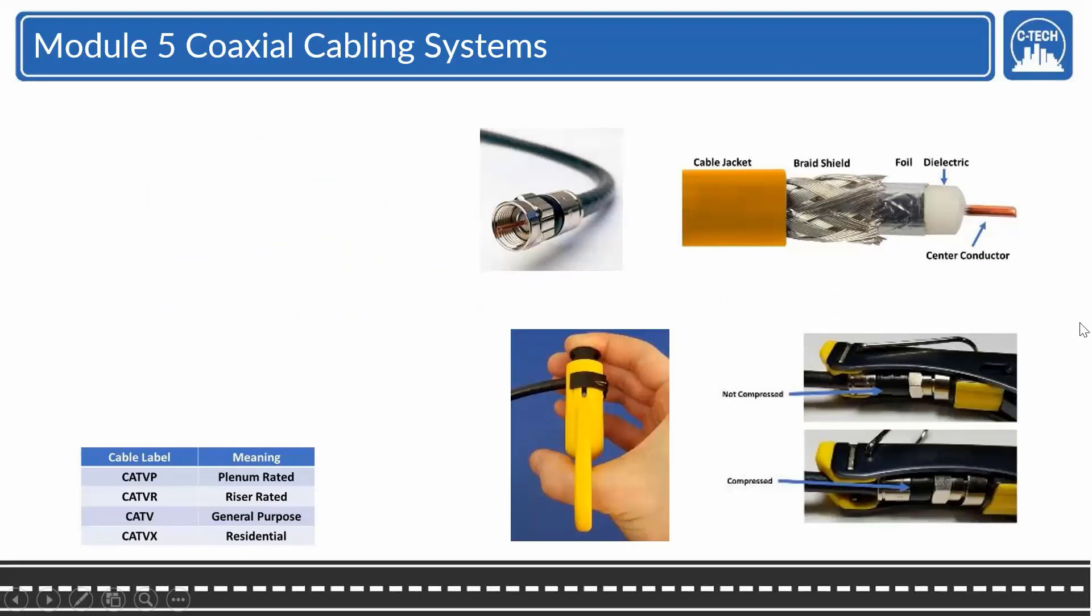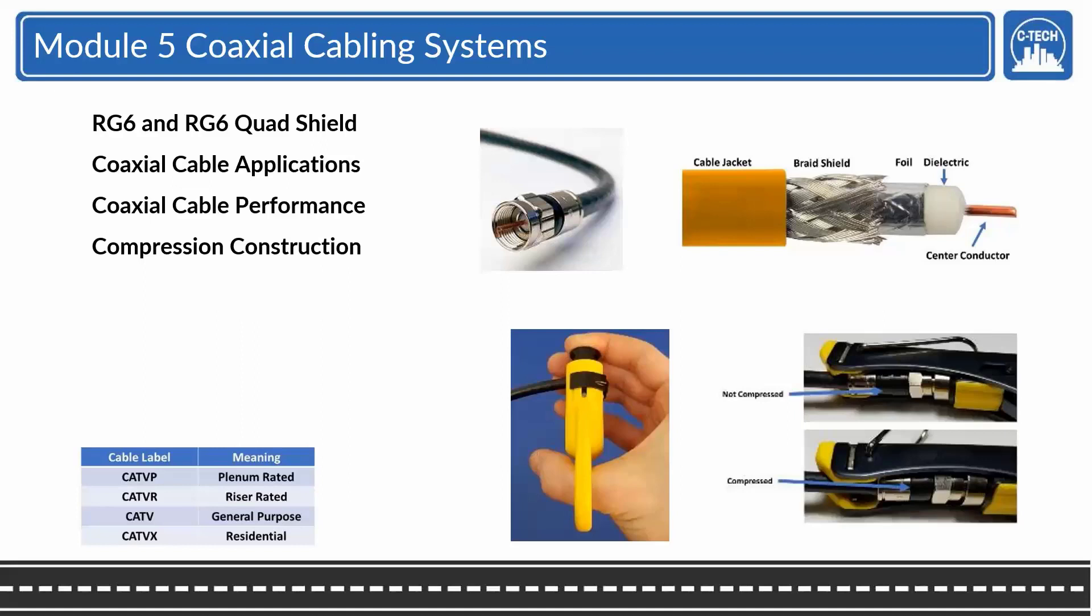Module 5, coaxial cabling systems. We're going to go all through the types of coax - RG6, RG6Q, which is what the standard recommends now. Q being quad shield. The applications, anywhere from baseband to broadband to DAS systems, which require rather thicker cables with N-type connectors. Performance, 75 ohm versus 50 ohm systems.